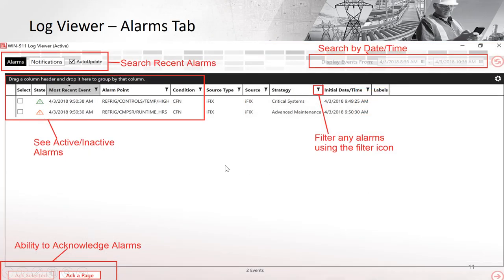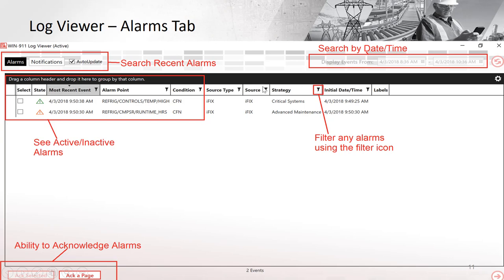Here's a detailed example. It shows the alarm, all the information it went to. Yours would have the System Platform source. This is just a demo and it shows you what strategy went to so you can double check to make sure the correct call-out list happened. You can use these little plus buttons to do some filtering and you can go back and search based on time of day to check to see what alarms happened. Finally, you can use this page as a method to acknowledge your alarms. You can check to make sure your WIN911 is connected to your SCADA.